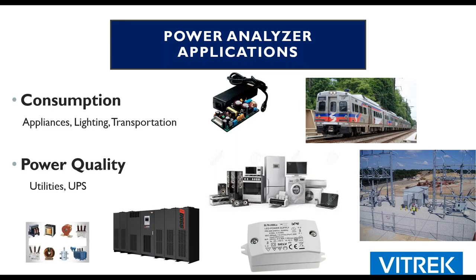To a lesser degree, power analyzers can also be used as a power quality device, although there are power quality analyzers out there in the market. But because of one particular feature of the Vitrek power analyzers, our history function, which I'll go into later in the presentation, you can hook our power analyzer up to utilities, a UPS type system, to do a long-term recording to find out how that power is being consumed or monitored. In the case of a UPS, UPSs typically just sit idle until you have a power issue. So once the power has gone out and the UPS kicks in, having that power quality monitoring capability on the Vitrek power analyzer would allow you to monitor the UPS and make sure everything is working as specified.